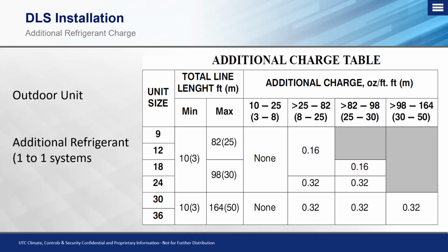Now let's just say that we ran 35 feet. Okay, well, we've got 35 feet. So if we take 35 feet minus the 25, which accounts for the charge in the outdoor unit and what it's good for, we're 10 foot over the design, which is 25 feet. So now what we'll do is take that 10 foot and multiply it by 0.16 ounces per foot. And that will give us our additional ounces that we need to add into the system based on our line set. Okay, and the most important part, it is ounces per foot, not pounds per foot.